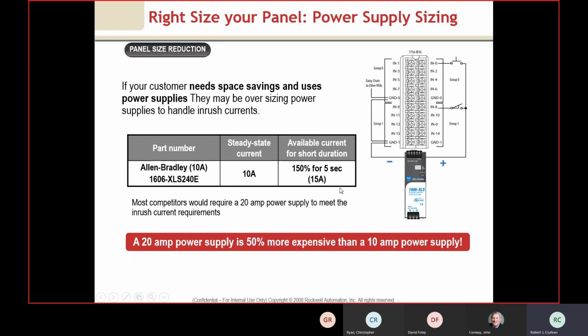So this will allow us to ride through those applications where your machine would shut down if you utilized a smaller power supply. And so this allows you to really optimize the application. So notice at the bottom, a 20 amp power supply is 50% more expensive. It's larger and provides more heat than a 10 amp.